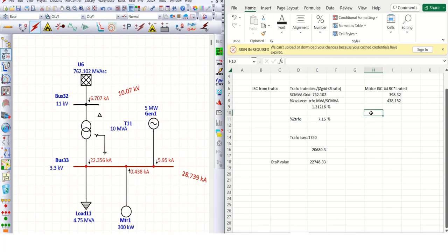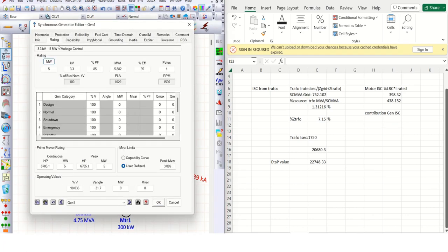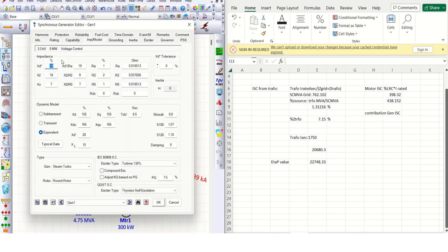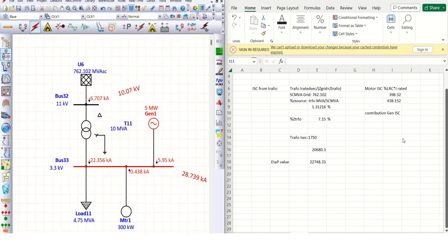Then similarly, the contribution from the generator. So how to calculate that? You just go to the rating page. Actually, this is a 5 megawatt rated machine. What factor decides the short circuit current contribution? Xd double dash, the subtransient reactance, decides your short circuit current. So 19%.